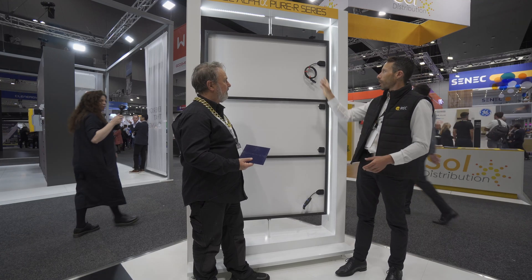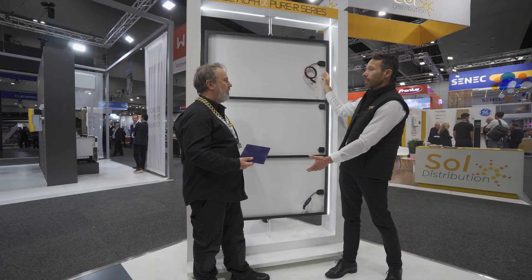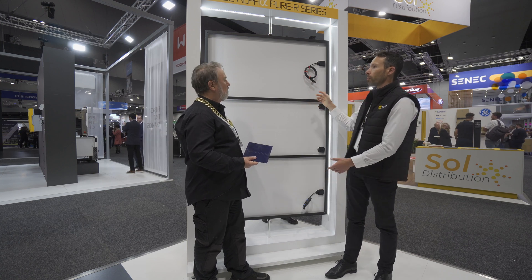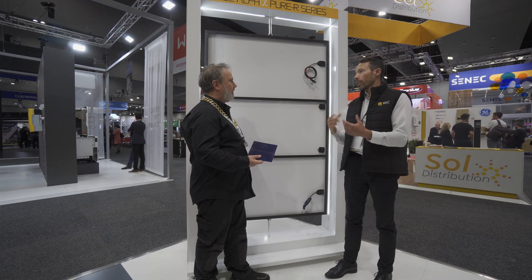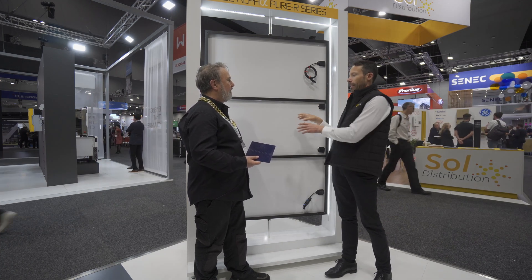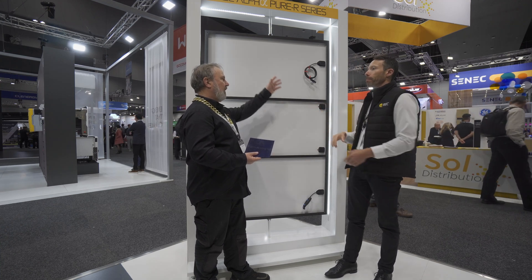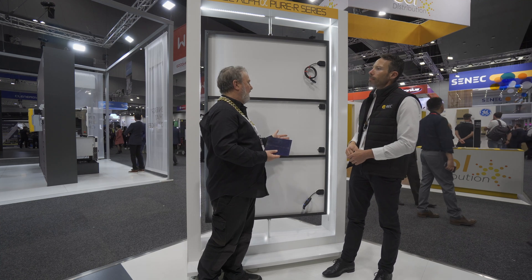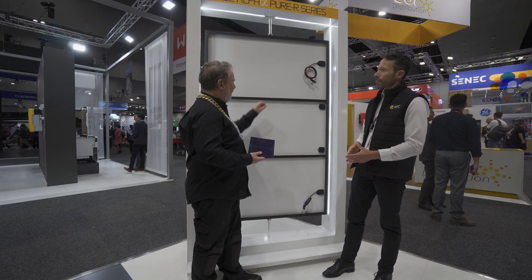As you can see, those are the junction boxes — it's a new design with four junction boxes. For the technical installer, there is quite a long lead of 1.7 meters to ensure cable management is done correctly, so the cable is not hanging under the panel or overbent. You can reach the rails that support the cables, and each of these junction boxes contains the bypass diodes.